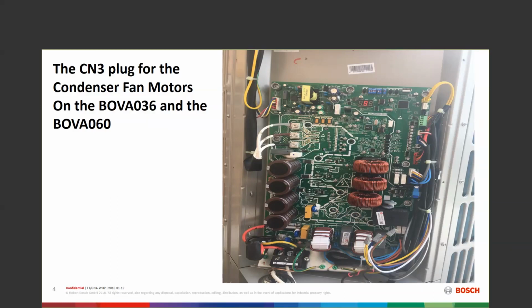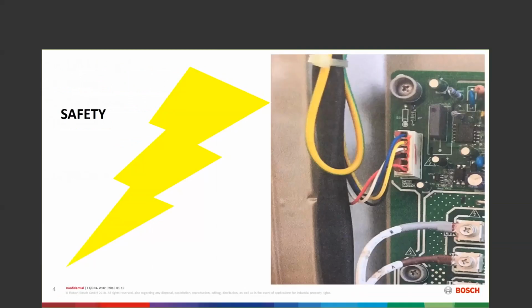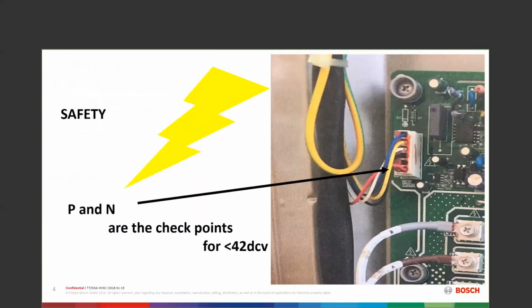But there is a connection part up here that allows me to look at points P and N. And when I look at those, what I'm looking for is less than 42 DC volts. So I'm going to put my voltmeter on DC, and I'm going to insert the leads into points P and N, and I'm looking for less than 42 DC volts. If I have less than that, then I am safely able to go into the board. If not, just wait a little bit longer. It's not a long period of time, but wait a little bit longer and then check it again before we go in there. That is your safety points.